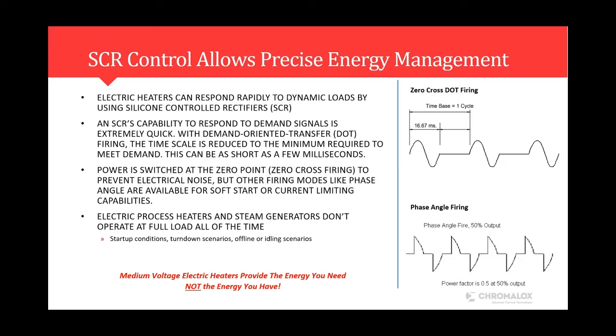So I've kind of alluded to it in a few cases here about the 0 to 100% turn down. Electric systems are very often controlled with what's called an SCR. Not to dive into all the nitty gritty and all the numbers, but basically these systems use proportional control, whether it be time-based or demand-oriented transfer. Basically all that means is that these things can shrink the time scale of how often the heater is on and off based on what your demand is. So if you have, say for example, a 1 second cycle time where this system is evaluating how much power it needs, and it's saying I need 10% power, this heater is going to fire for 1/10 of a second, and then it's going to be off for 9/10 of a second. So you're basically using exactly the energy you need, not necessarily all of your power.